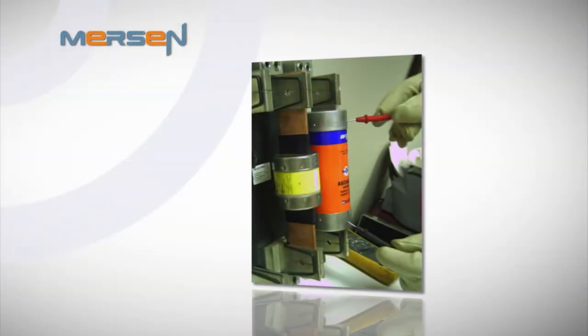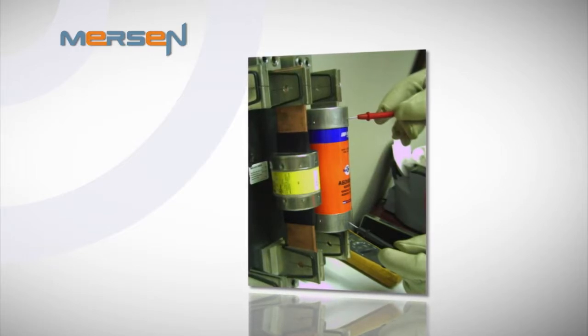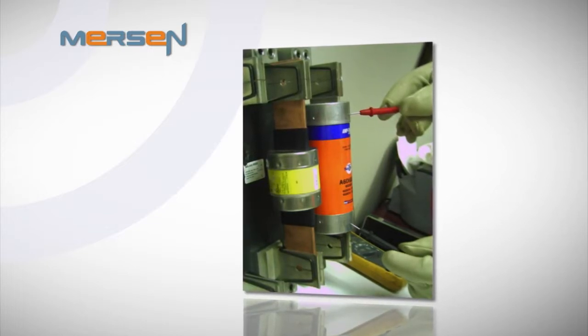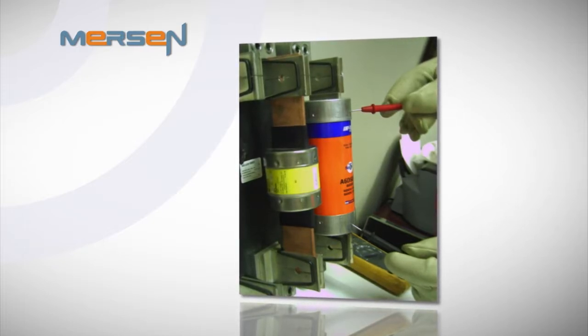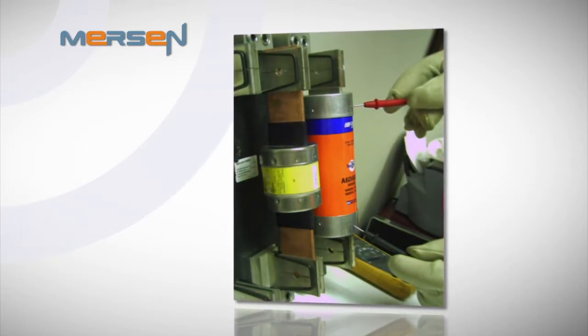Mersen's test method keeps your people, plant, and equipment safe. OSHA requires lockout-tagout procedures that include testing for the absence of circuit voltage. Historically, people have used the fuse end caps for a convenient test location. Fuses with disconnected and insulated end caps can appear to be de-energized when they are not. As an industry leader, Mersen continues to provide electrical contact between the fuse element and the end caps to maintain customer safety.